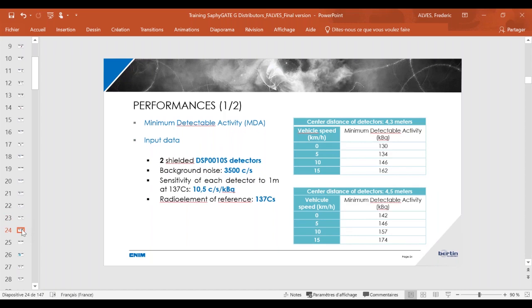Now let's look at the performances of the system. If we consider two shielded DSP0010S detectors, the detectors on the SaphyGATE G, we consider a background around 3,500 counts per second, and sensitivity with a reference radio element, which is cesium. You have the minimum detectable activities presented here.